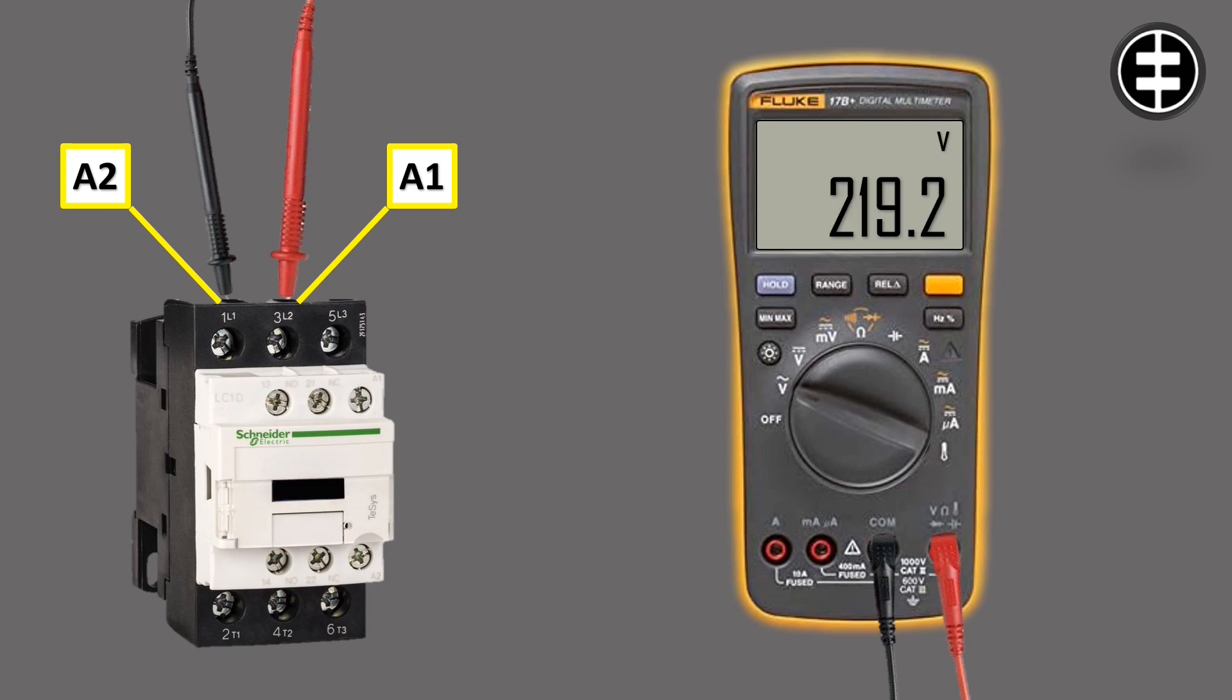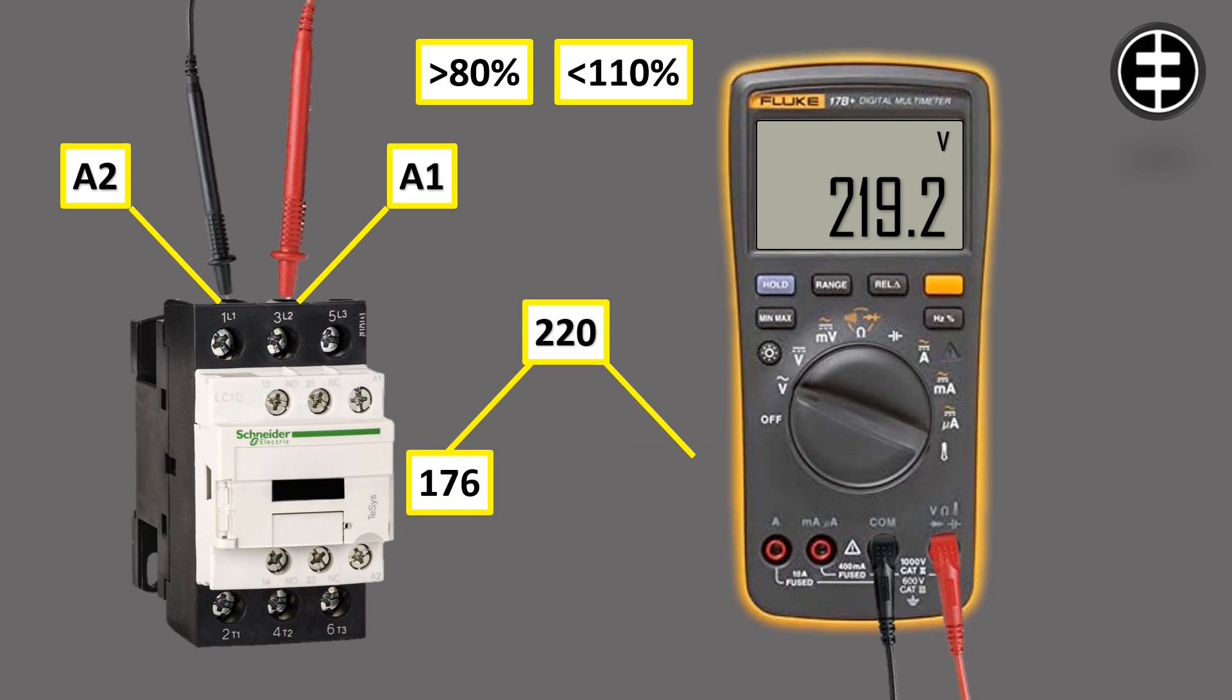It should be more than 80% and less than 110% of the coil nominal voltage. For example, if the contactor coil voltage is 220 volts, the accepted measurement should be from 176 volts to 242 volts.